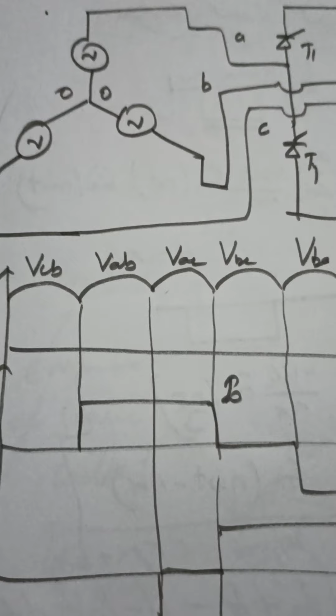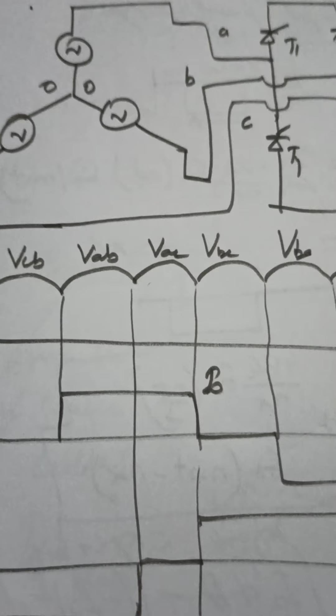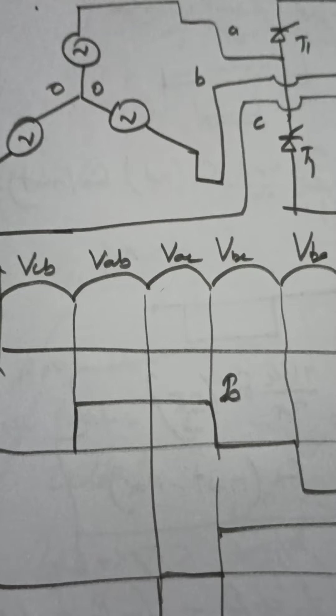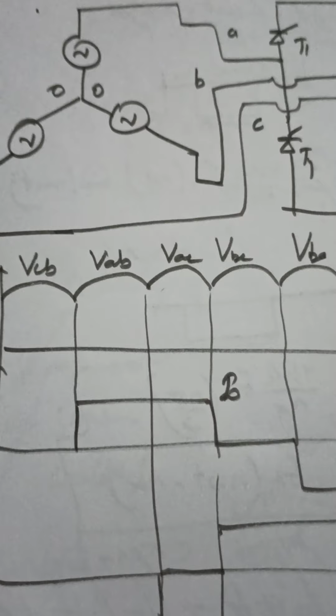But after that, when the power is received at the receiving end, the requirement of a three-phase inverter at the receiving end and a three-phase rectifier at the sending end becomes imminent. It means both are of very wide importance. Why? Because the electricity that is transferred to the HVDC link is transferred via a three-phase rectifier. That three-phase rectifier will convert the heavy high-voltage electricity into DC form. So the rating of the thyristor, the thyristor current carrying capability, and the input power factor all become very important. I can say they play a pivotal role in deciding the overall structure of the power system.